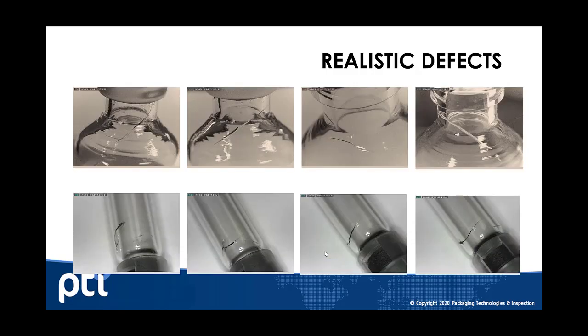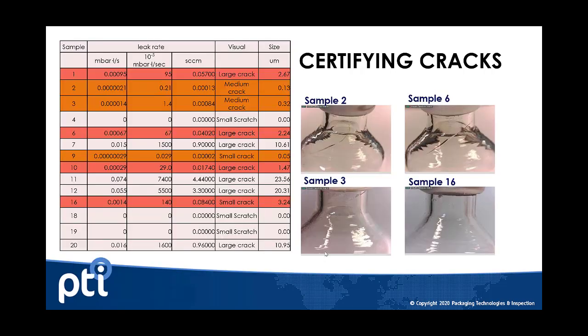Cracks are very unique and different, and they vary in their geometry. After the fact, you actually have to validate that leak size against a certified flow measurement. In this case, helium was used — we created these defects and then certified that leak size against helium leak rates. That gave us a wide range of defect sizes, and you can see that a crack can produce defects below 1 micron as well as above 10 microns.